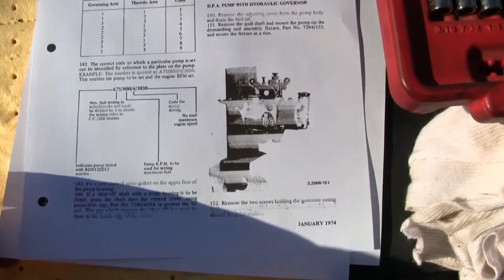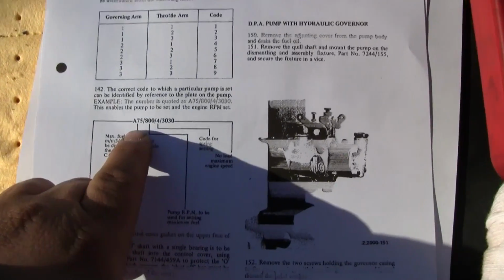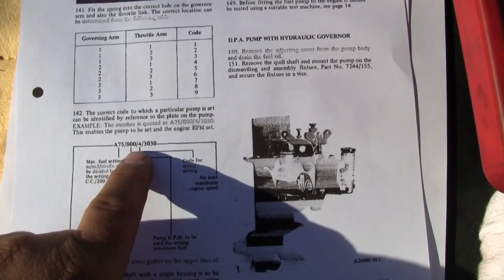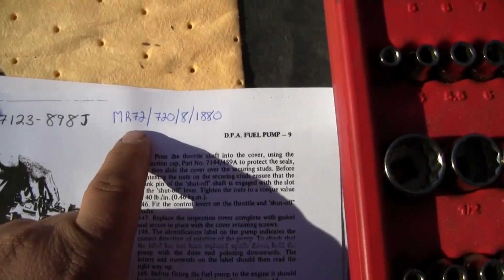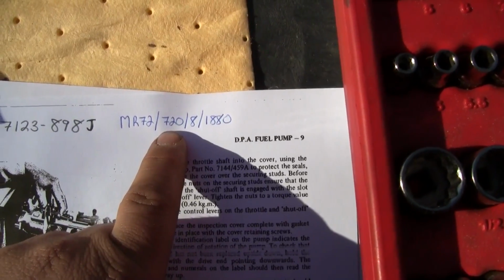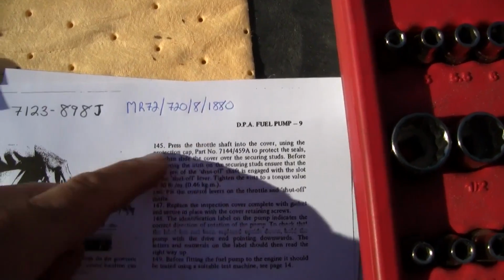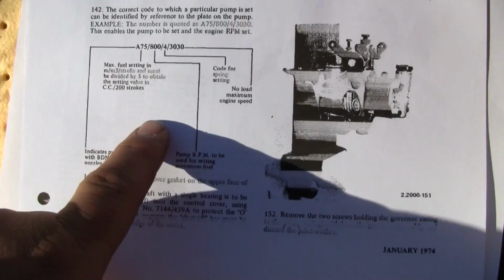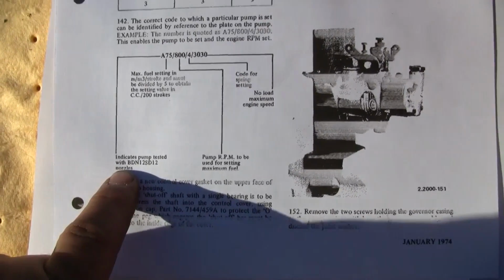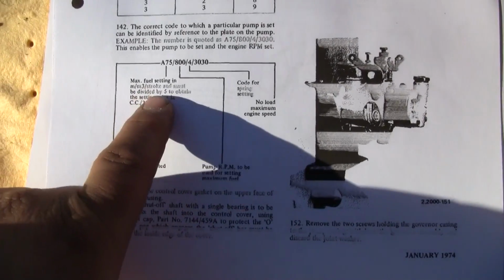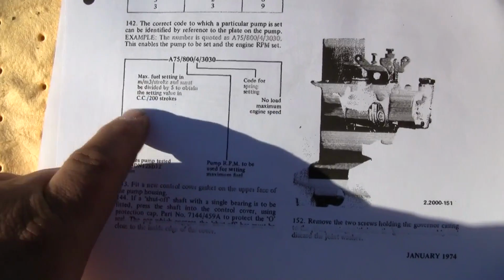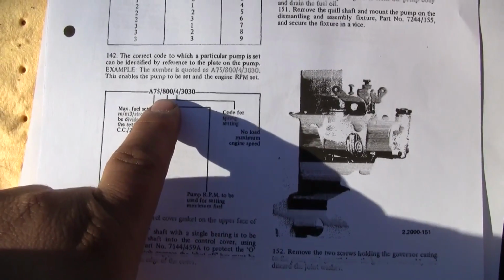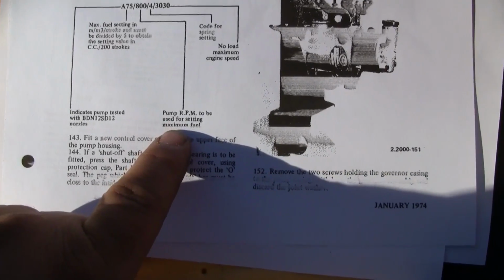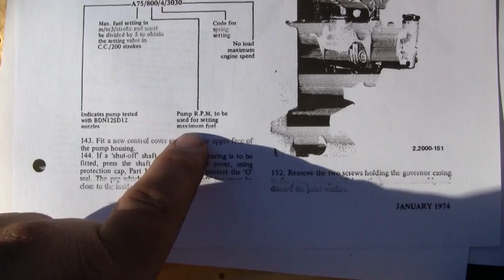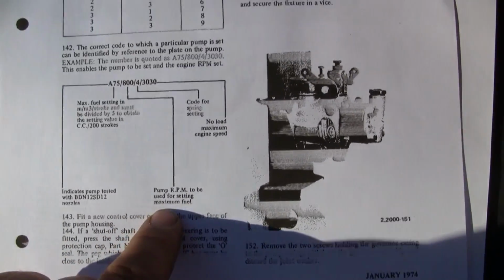Secondly, we have some more important information here, decoding the code number stamped on the injection pump's tag. Here is my code on the pump: MR72/720/8/1880. Based on this decode, we know the type of injector nozzles the pump should be calibrated with - not really relevant to me, as well as the maximum fuel setting, again not relevant since I don't have a test bench. In this case, 800 was the example, which is the pump RPM needed to calibrate max fuel - not relevant for me. Mine happens to be 720.